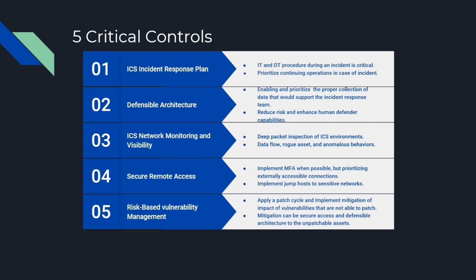In OT environments, we not only deal with different components, we deal with legacy systems. Like I said, if the system is not reliable, it's not secure. OT environments are designed to have a 10 to 30-year life cycle management. So sometimes the remedy could be worse than the sickness. If we apply a patch that breaks the HMI application, that's not reliable anymore. Therefore, the process is not secure.